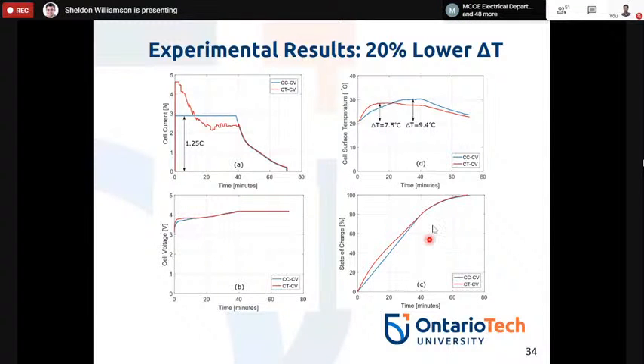Yes, the charging times are now the same, but the cost is a 2 degree Celsius rise, going over the 8 degree Celsius cutoff to 9.5 degrees. As I said, even 0.1 or 0.2 degree Celsius rise causes capacity fade, we have seen up to 10% fade in capacity.